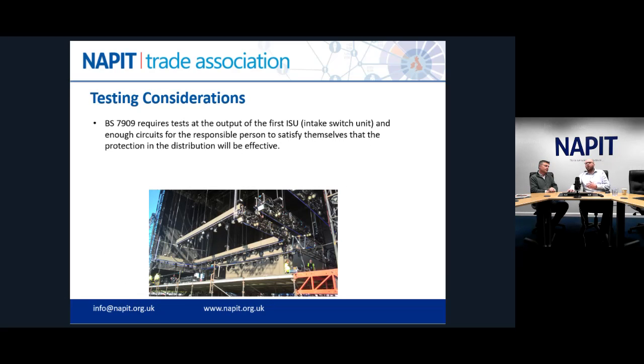So BS 7909 requires that tests are carried out at the first intake switch unit and that enough circuits are tested so that you can satisfy yourself. As we pointed out, intake switch unit is an old TV term. It's basically the first distribution unit you get to from the source of supply. So if you have your generator, the first distribution unit will be the ISU. And as we've seen, because we might have hundreds, if not thousands of circuits running around the place, you can't go and test each one individually because it would take forever. That's why the senior person needs to look at the design and decide which parts of the distribution he wants to test to make sure that he can satisfy himself the protection works.